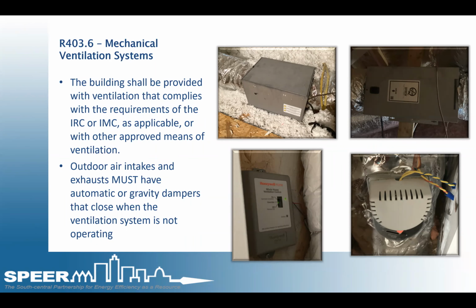R403.6, mechanical ventilation systems, also known as fresh air. The big question always comes up for me: do houses need to breathe? The answer to that is yes, and we want to control when and how much, not uncontrollably. As homes are built tighter and tighter, the chances of having good indoor air quality start to quickly diminish. In order to keep the bad at acceptable levels, the indoor air must be either exhausted to the outside or diluted with incoming air from the outside.